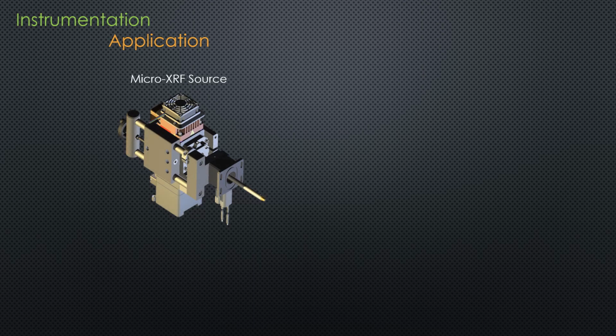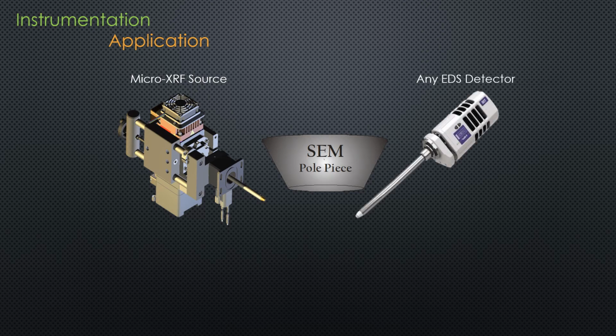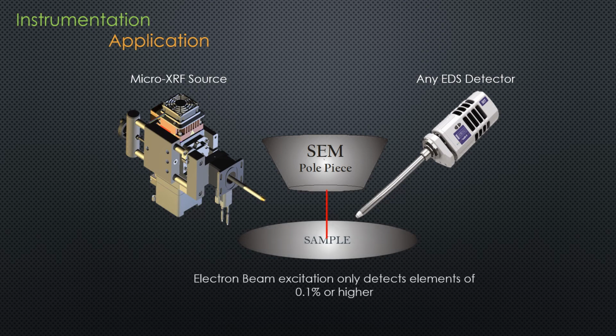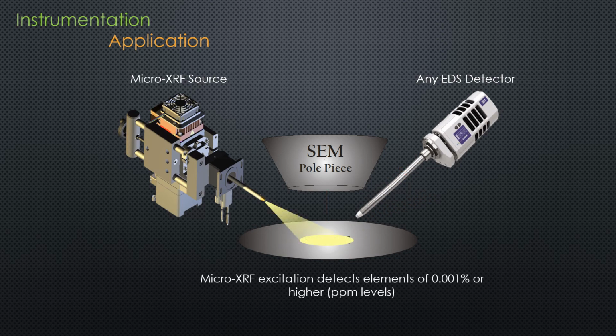Here we have our source. Any EDS detector. Electron beam excitation can typically excite elements down to about 0.1%. Of course, you can see elements a little bit lower, but as a textbook rule, it's about 0.1%, depending on the element. With Micro XRF excitation, we can see pretty much all the traces down to about 10 to 5 ppm, depending on which element.